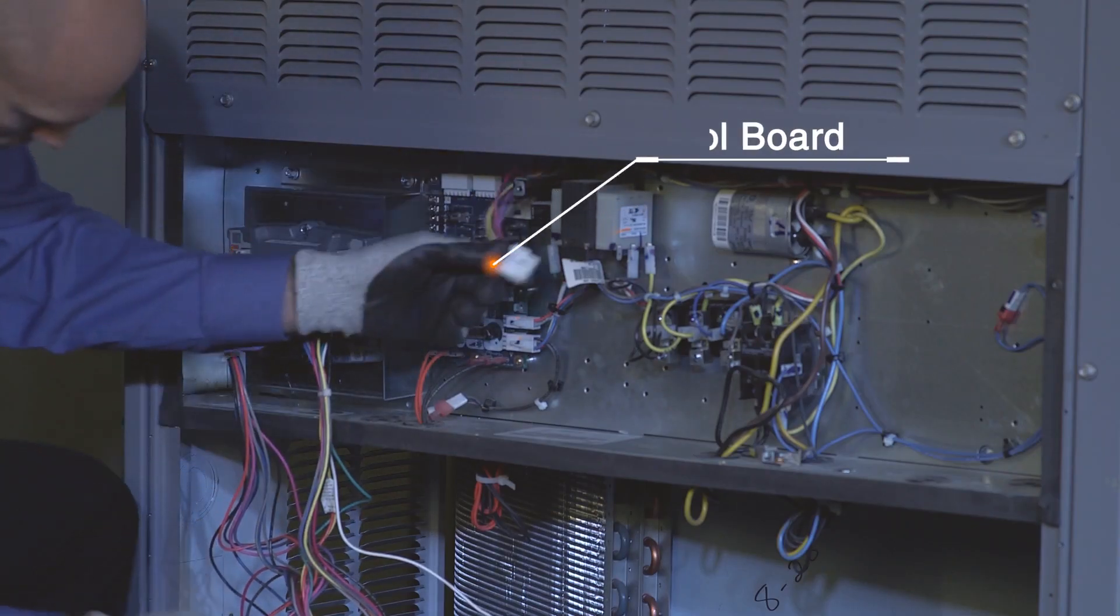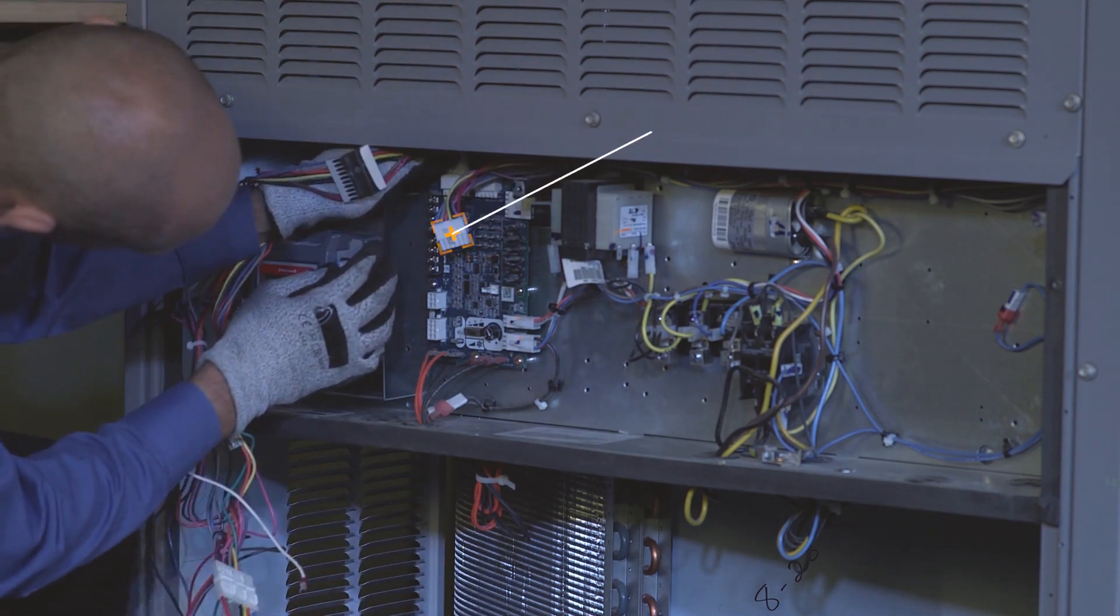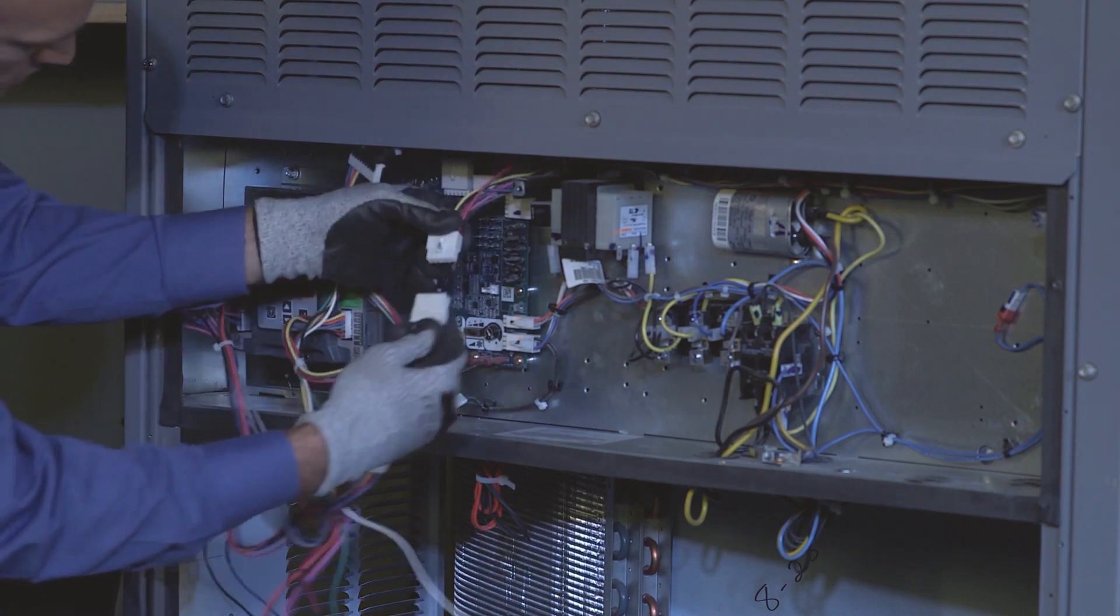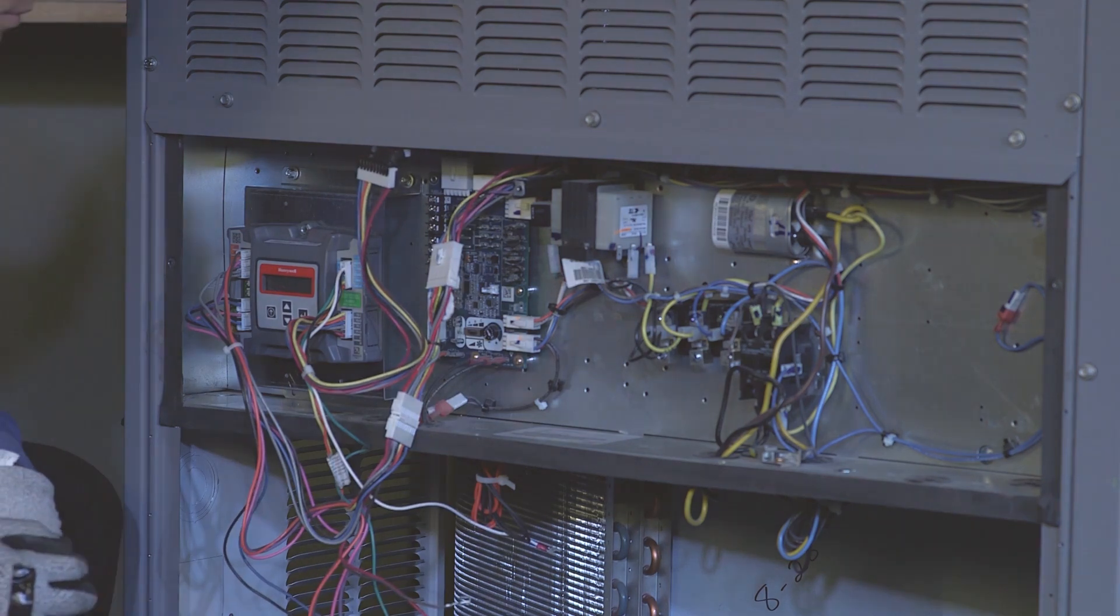Disconnect the 12-pin male plug from the unit control board and connect the 12-pin male from the W7220 in its place. Connect the 12-pin female plug from the W7220 to the male 12-pin plug.